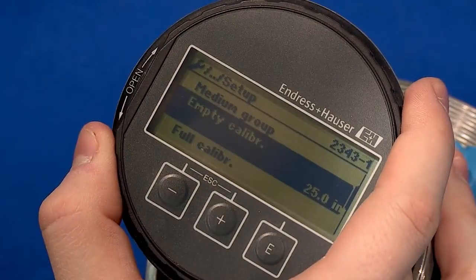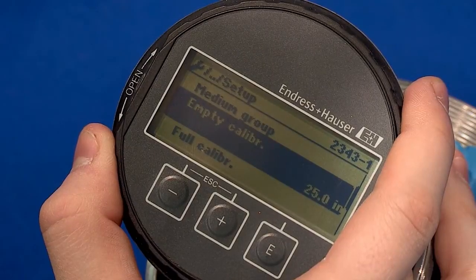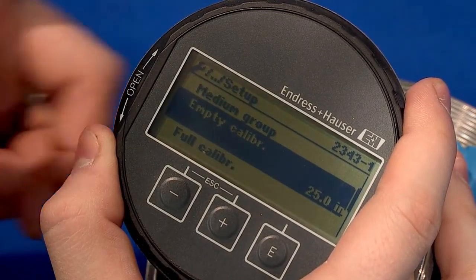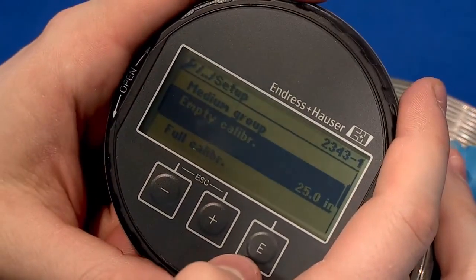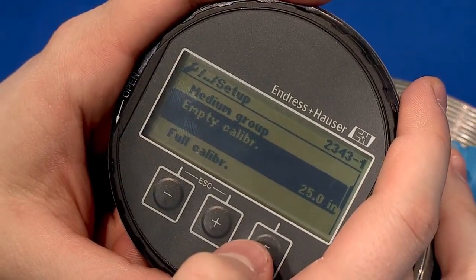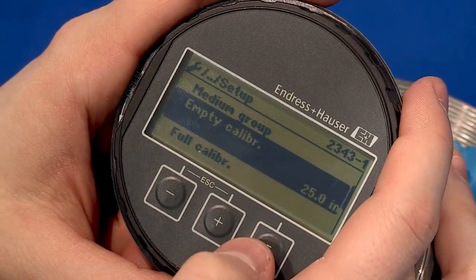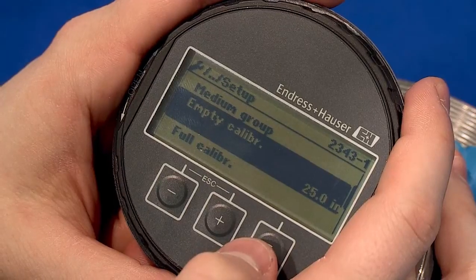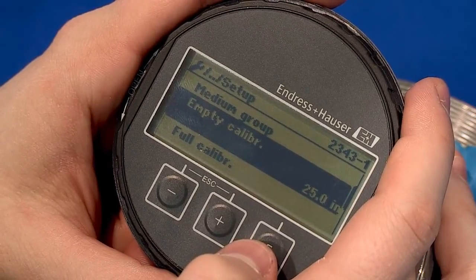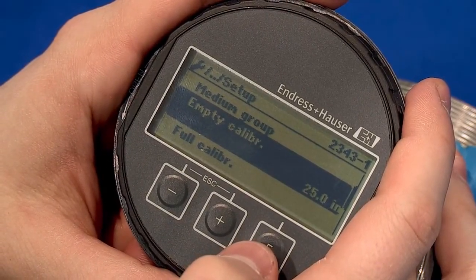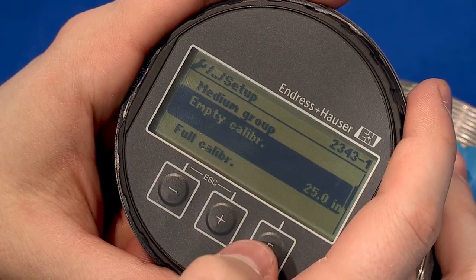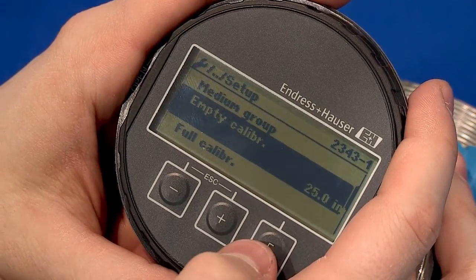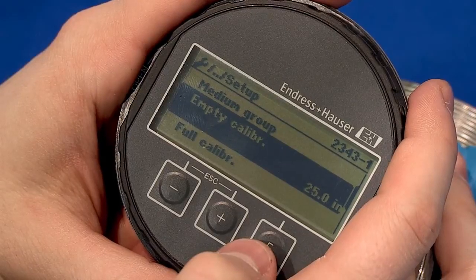The fourth parameter in the setup is the empty calibration. This is the distance from the process connection to your 0 point. For example, if your probe is 30 inches and you want to read all the way to the bottom of the probe, you will enter 30 inches for your empty calibration. You may select your 0 wherever you would like it on the probe. However, your empty calibration will never be 0.